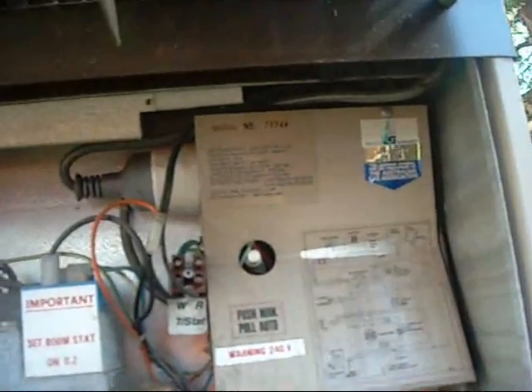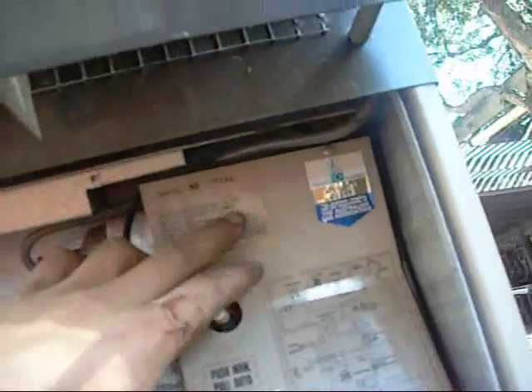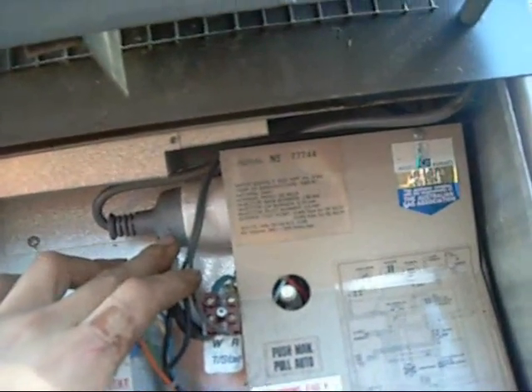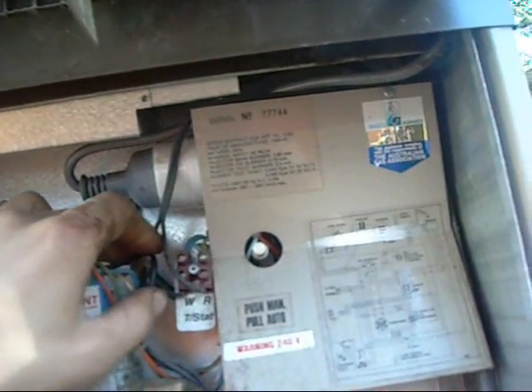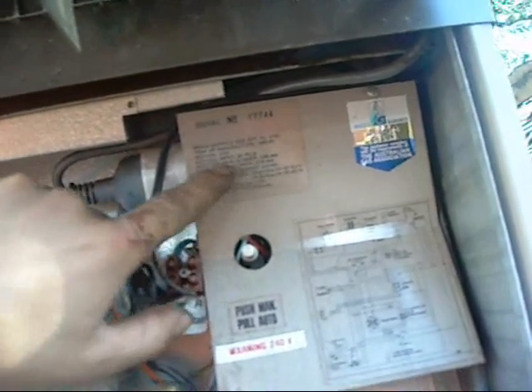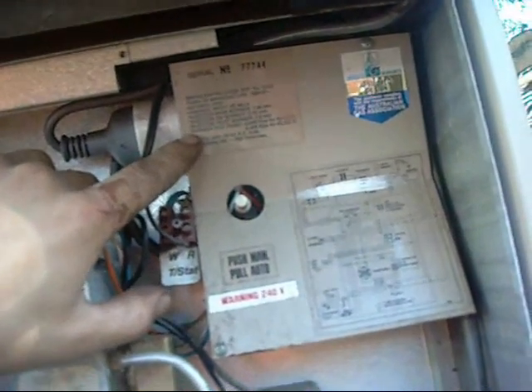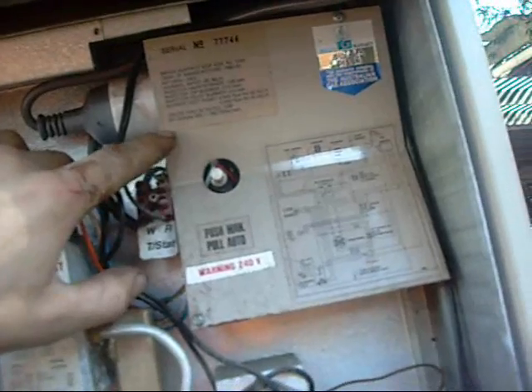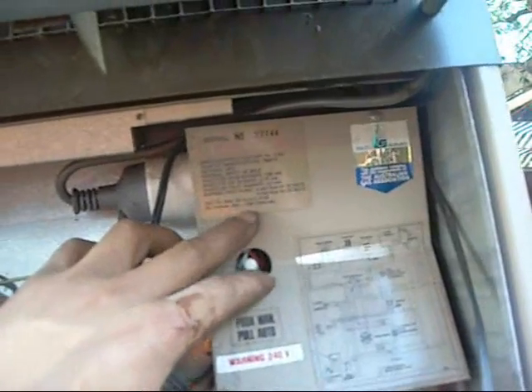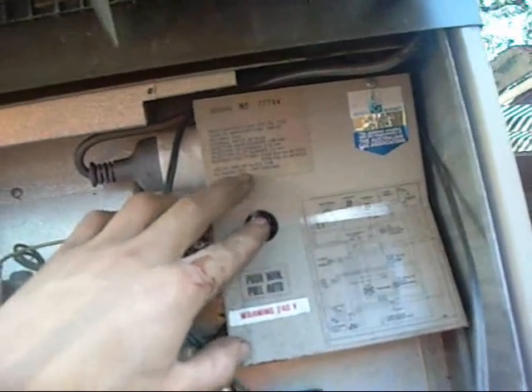quite a dependable machine. It's a 1990-1991 manufacture, natural gas, 85 megajoules an hour input, 1.95mm main burner port, and standard 240 volt single phase fan motor and control, 24 volt indoor room control. Air volume 580 litres per second, or 260 to 580 depending on fan speed, I suppose.